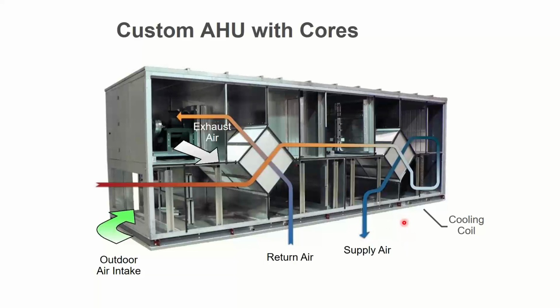You could also get hot gas reheat off a compressor. You could have solar panels on a roof, right? Solar thermal panels. But in this case, my air came in, dropped off some of its heat that it already had, got subcooled nice and low to wring a lot of moisture out of it, wrapped back around, and picked up some BTUs to temper it back up to 63 or 65 or 70 degrees or whatever they needed.